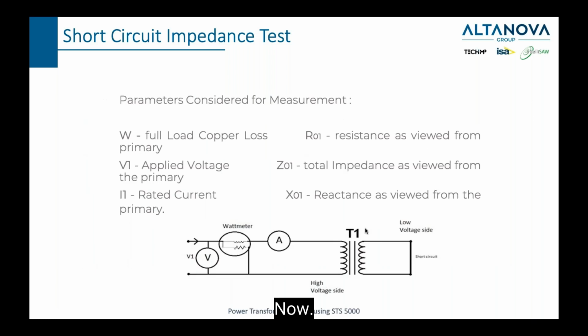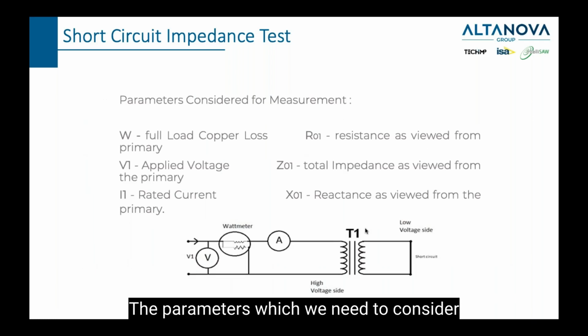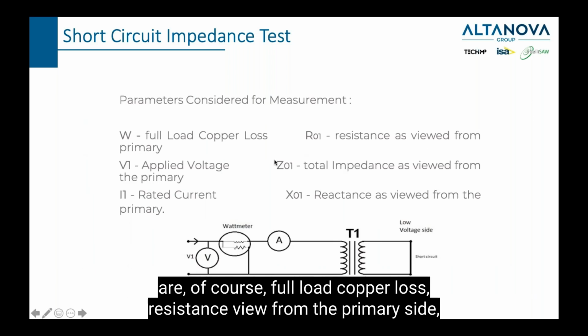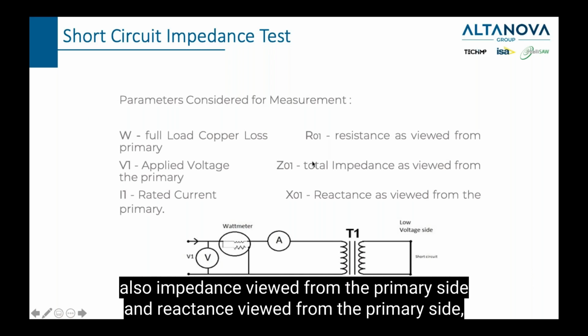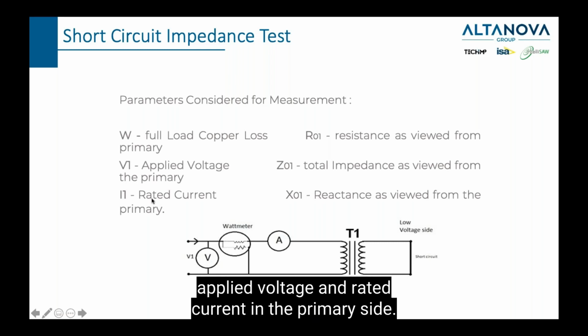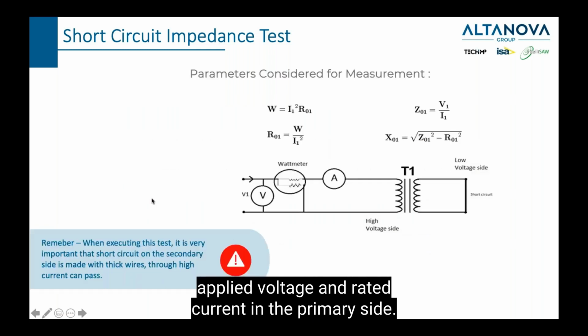Now, the parameters which we need to consider are, of course, full load copper loss, resistance viewed from the primary side, also impedance viewed from the primary side, and reactance viewed from the primary side, applied voltage, and rated current in the primary side.